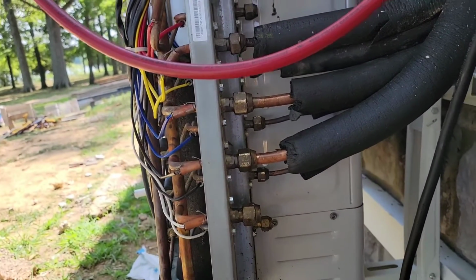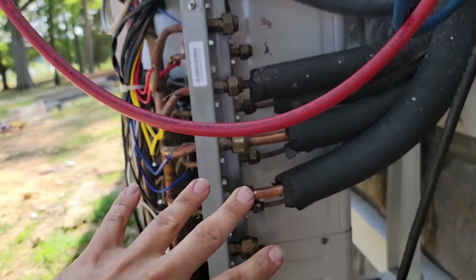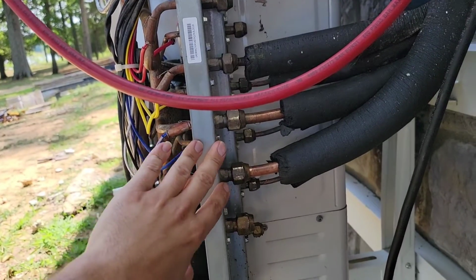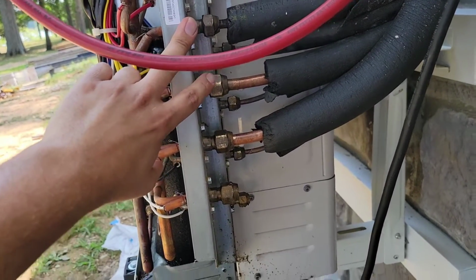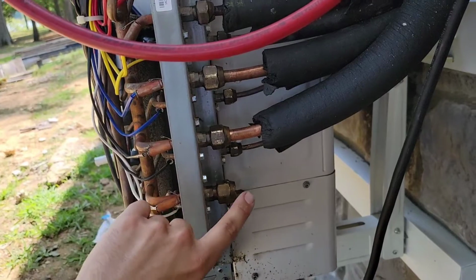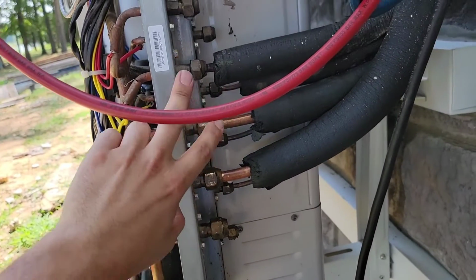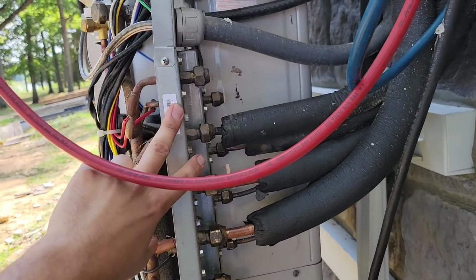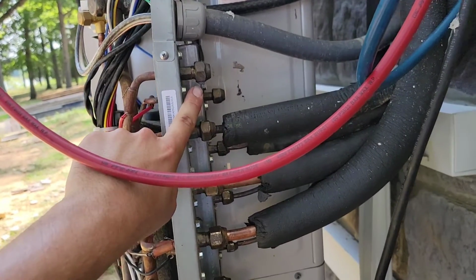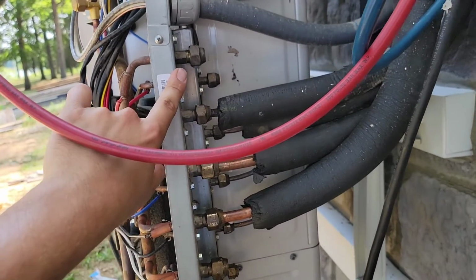Now this should tell you something. In your installation manual, it definitely shows you how this should be hooked up. The line set that is going to be the longest goes on the bottom. And you also have to pay attention to your installation manual because it's going to tell you the BTU per unit and what pipe connection you should put it on.